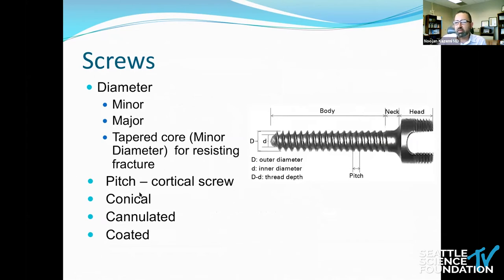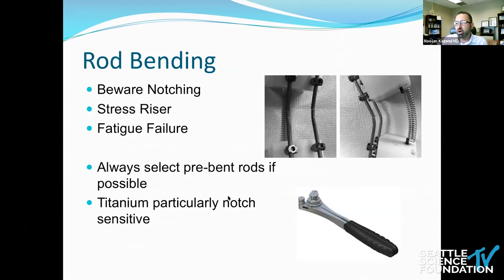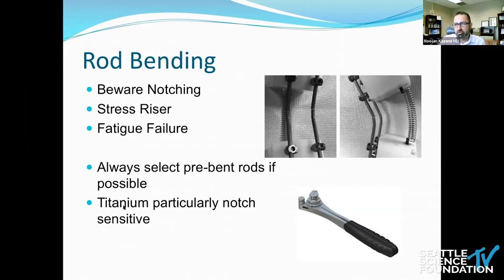Regarding screws, there is an inner diameter linked to strength, an outer diameter, and the pitch between the threads — they can be cannulated and coated with hydroxyapatite for osseointegration. For rods, an important point: when you create notching by bending a rod, you create a stress riser — a place of weakness across which fatigue may develop over time, particularly across cyclical loads. Always select pre-bent rods if possible. This is less of an issue for cobalt chrome but much more so for titanium. For deformity surgery, we now add additional rods such as a tri or quad construct to overcome this weakness of titanium alloy.